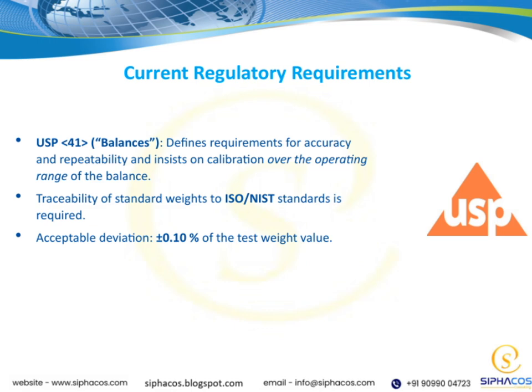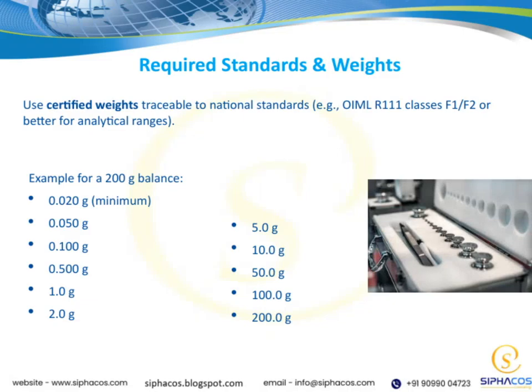Overall, these requirements highlight the importance of precision, traceability, and consistency in weighing to meet regulatory standards and ensure high-quality results in your processes. When it comes to using weights for calibration and verification, it's essential to rely on certified weights that are traceable to national standards. For example, weights classified under OIML R111, such as F1 or F2 classes, or even better, are recommended for ensuring accuracy across analytical ranges.